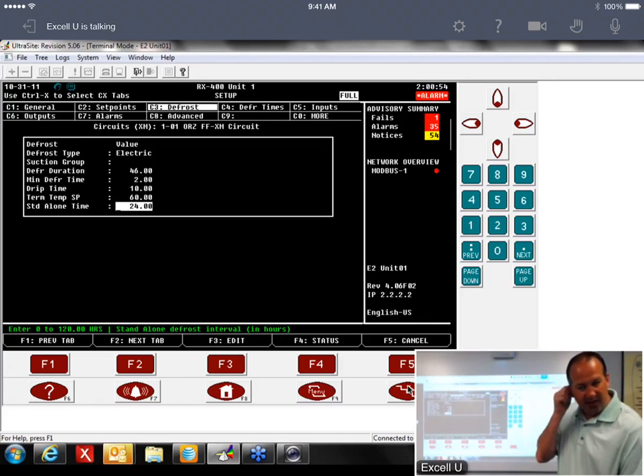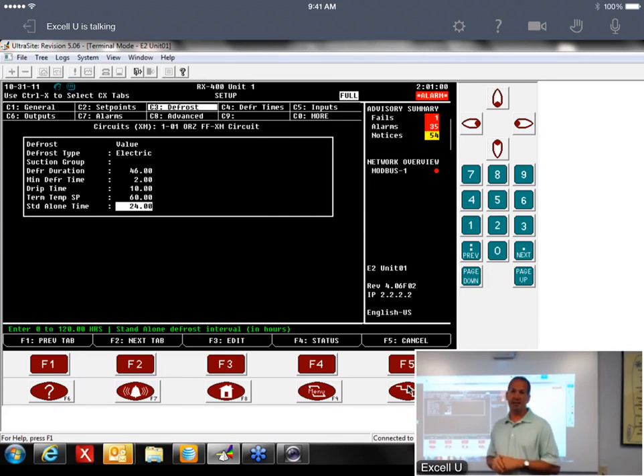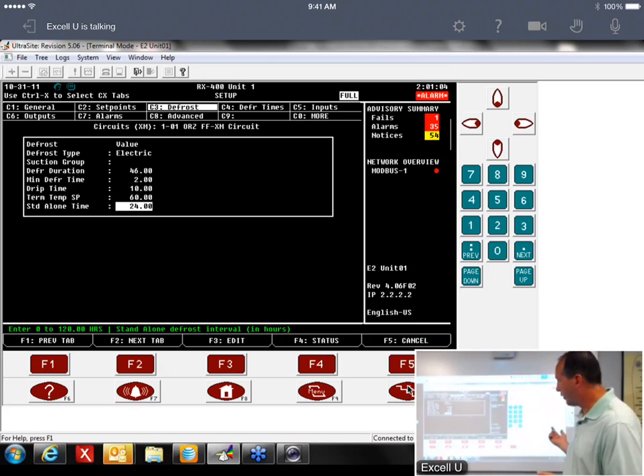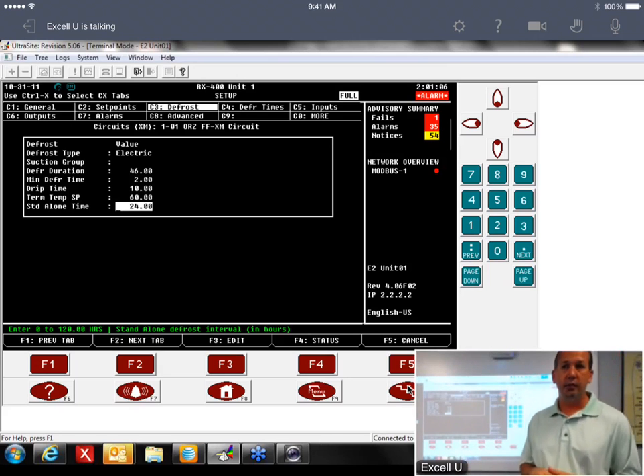And I believe that defaults at 4 defrosts a day, which is 6 hours. So if you have 3, you have to change it to 8. If you have 1, change it to 24. If you have 2, change it to 12. So it's however many hours between defrosts you want it to be.